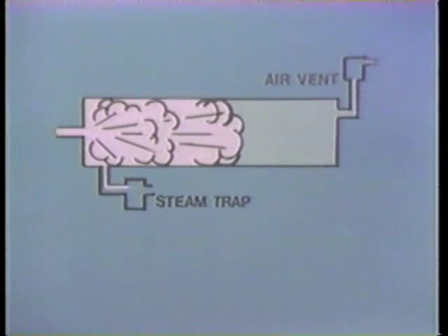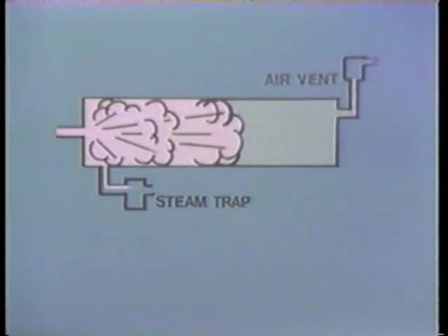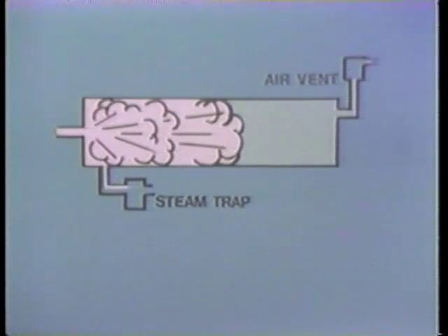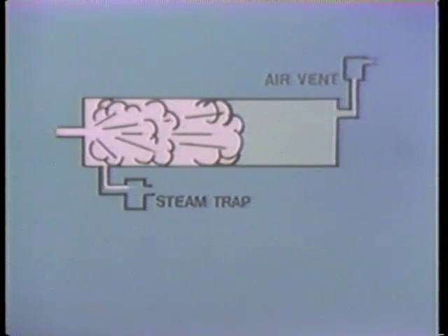In this type of heat exchanger, the steam inlet and condensate drain are on the same end of the steam space. The steam pushes the air to the right side of the space where it becomes trapped, forming a cold spot on the heat exchange surface. Some of the air mixes with the steam and the rest forms a cold pocket, resulting in uneven heating. To remove the air from this space, a thermostatic air vent should be installed at the end of the heat exchanger opposite the steam inlet and condensate drain.